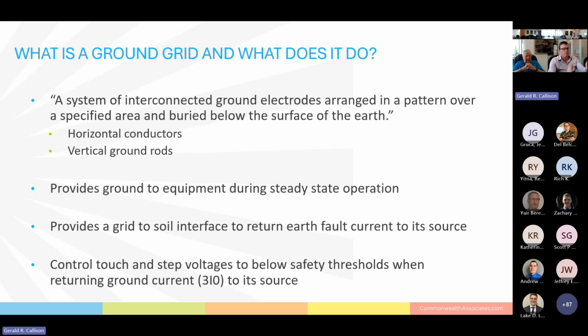So with that, what on earth is a ground grid in the first place? A ground grid is a combination of horizontal conductors and vertical ground rods that are buried in a pattern across a specified area below a substation. Now, why on earth are we putting this copper, which is prone to theft, underneath the substation to begin with?